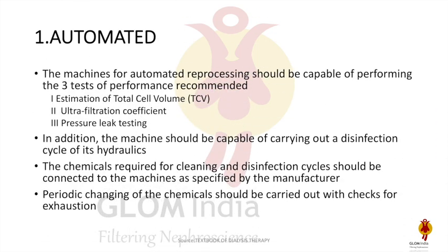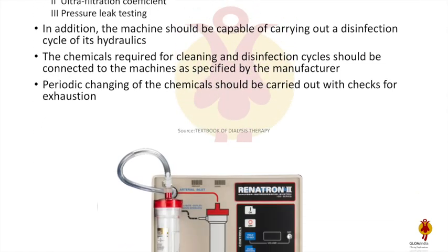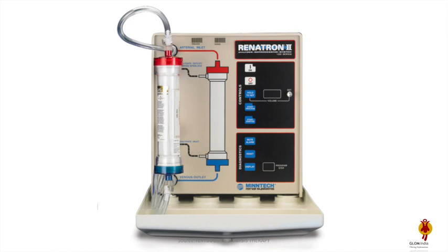There are two methods of reuse: automated and manual. For the automated method, machines are available that check performance using three tests: estimation of total cell volume, ultrafiltration coefficient, and pressure leak testing. The machine should be capable of carrying out a disinfection cycle of its hydraulics, and the chemical required for cleaning and disinfection should be connected as specified by the manufacturer, with periodic checking for exhaustion.